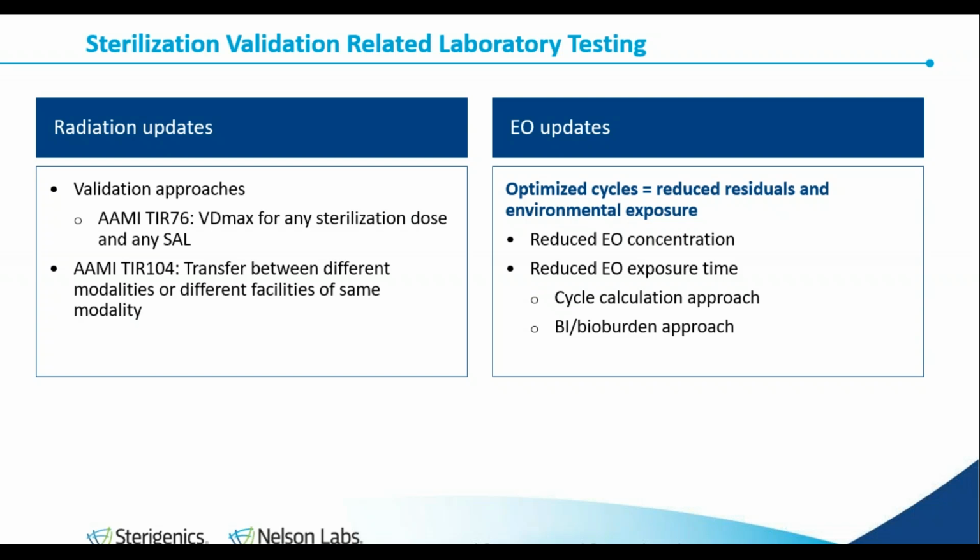On the ethylene oxide side, just to make you aware, what we're seeing in the industry a lot in the last couple of years is a greater focus on more optimized sterilization cycles, rather than just defaulting to these long cycles because you can fit lots of product under that one family. Having more optimized cycles that spend less time in the chamber and therefore have fewer residuals.